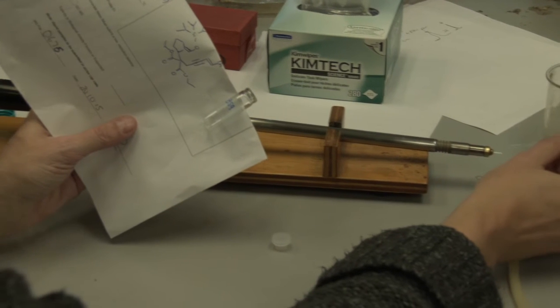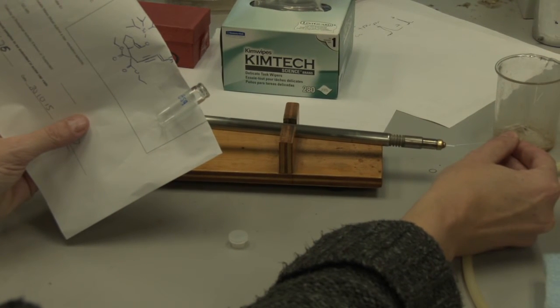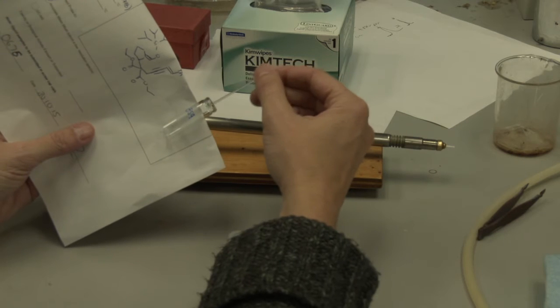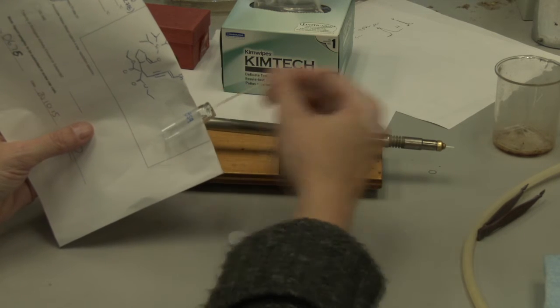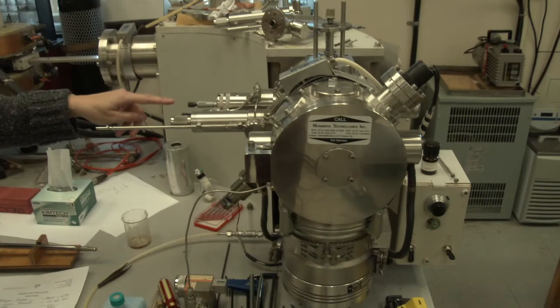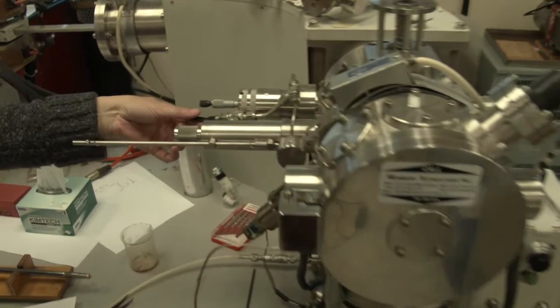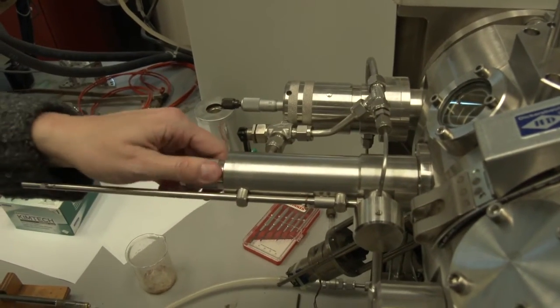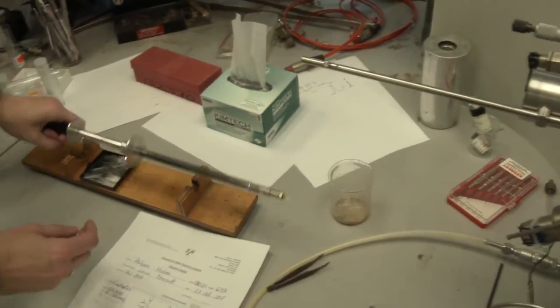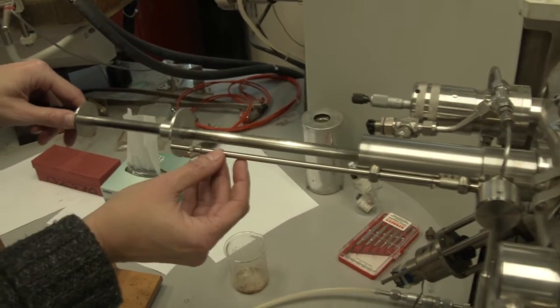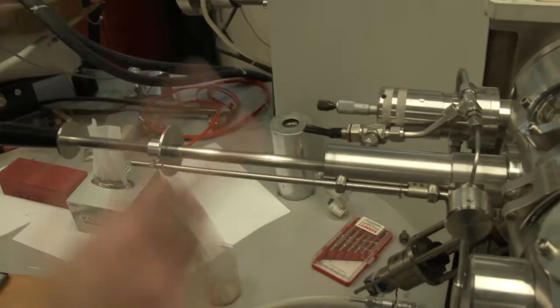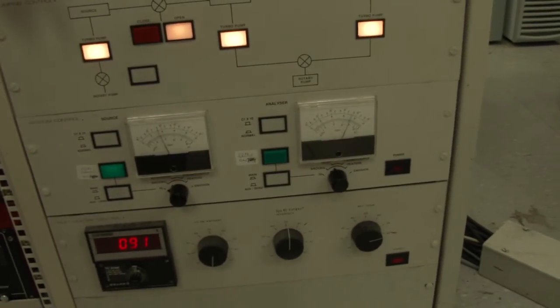Philip's sample is taken out and a small amount is placed inside a glass capillary that is inserted at the end of a probe. An electron impact source is within the interior of the vacuum, so to get the probe into the source, the vacuum is broken and restored in 2 stages. The probe is first inserted into the extension to the source, which is separated from the main source interior by a gate. This section is brought up to air by first turning off the roughing pump and then opening the section by removing this bung. The probe is then carefully inserted into the hole, which seals it, and the roughing pump can then be turned on and the pump gauge is monitored to see the decrease in pressure.